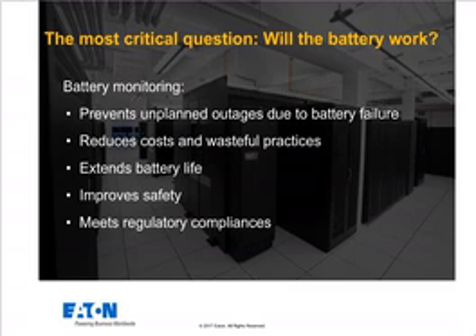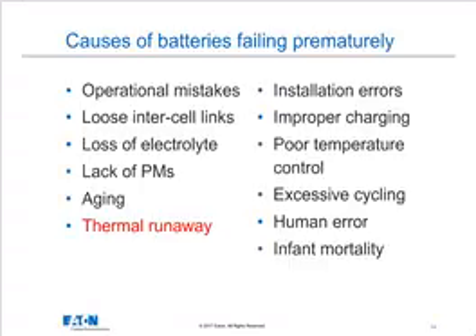A lot of our clients have very large investments in batteries, and they want to know everything they can about every battery in the system so that they can feel comfortable that when they need that battery, the capacity is going to be there. So battery monitoring systems can be added to existing battery systems, and they prevent unplanned outages. They reduce cost and wasteful practices. They should extend the battery life if it's a properly designed system, and also improve the safety for the people that are working around the battery. They let them know if an unsafe condition exists, and make sure that your large industrial battery system meets regulatory compliances. And we'll talk about those as we go through. So moving on to the next slide here.